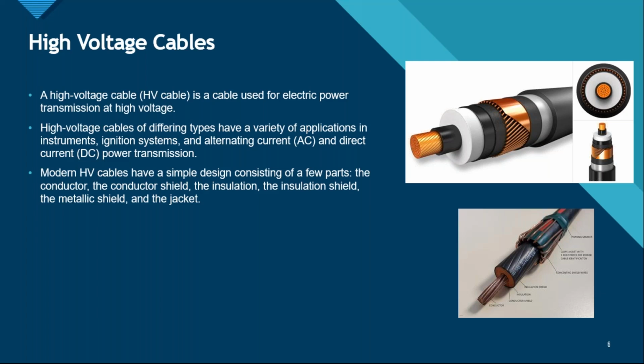the overall jacket. Usually when we talk about the normal domestic wiring or the electrical wiring that we usually deal with, they have double insulated cables, right? They have the core, the conductor. If it's a three-phase supply, there are four cables inside, right? For three phases and a neutral. Individually they are insulated, and there is an overall insulation as well. But for a high voltage cable, it is much more hazardous. So it needs to have the additional insulation shields, the metallic shield, and the jacket as well.